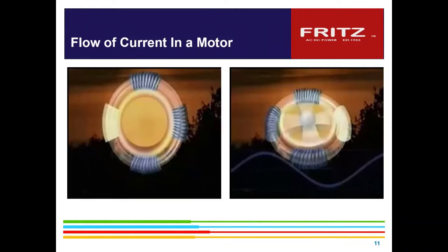So what he was showing in the video is that there are coils in the motor, and as you apply alternating current to it, it creates a north and south pole and makes the motor shaft rotate. Well, when we provide 60 cycle power, like in America, to a 4-pole motor, the synchronous speed would be 1800 RPM, but it's more like 1725. It doesn't change from that speed as long as the frequency is the same. So for years it was very complicated to figure out ways to vary that. The only way you could actually do it would be to slow the generators down and slow the sine wave coming from the rotating machine.